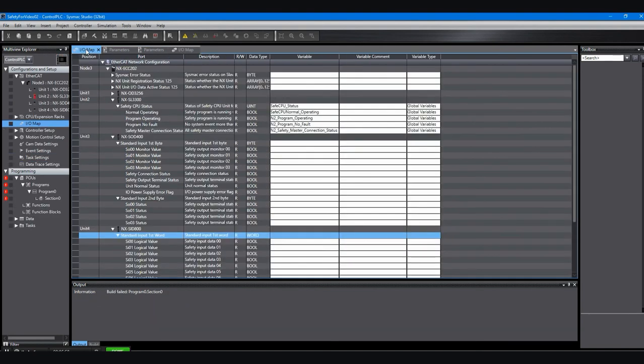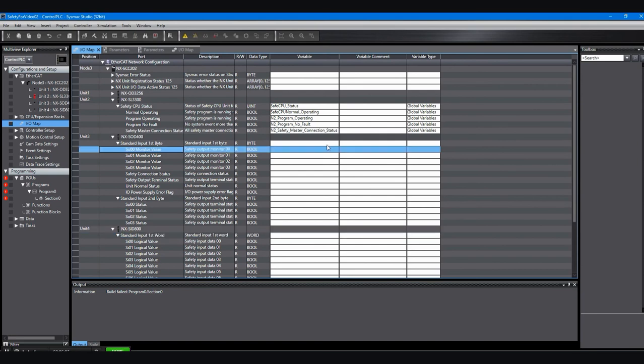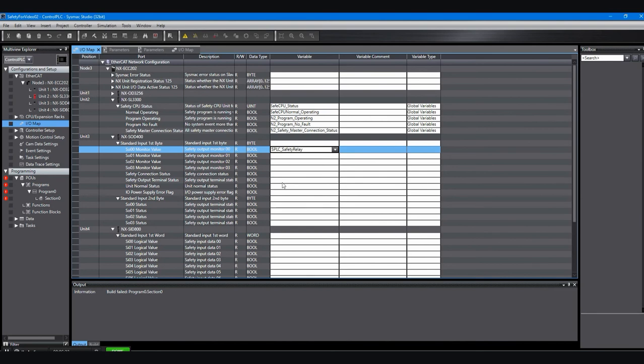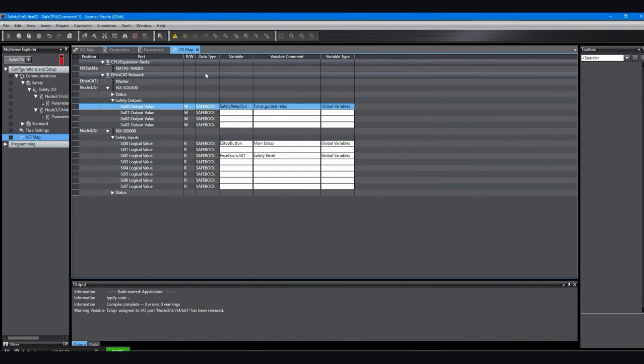But now we can go back to the control PLC IO map. This is the control PLC. This is where we were before. Now that we know what the assignments are for the safety PLC inputs and outputs, we can create variables over here in this control PLC. They don't have to be the same names. They can be completely different names. And what this will allow you to do is monitor the inputs and outputs of the safety PLC directly in the control PLC without having to write any code or communication code or anything like that.